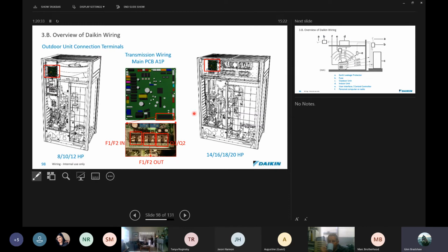Communication wiring in the outdoor unit. These are found on the control PC board, the A1P PC board. You'll find that on the 8, 10, and 12 in this vicinity of the wiring box, and on the 14, 16, 18, and 20, you'll find it over here, the terminal strip in the bottom right corner. They're designated F1, F2 in, remember, going to the indoor units, F1, F2 out, going to a centralized controller or my laptop, or the Q1, Q2, which would connect to other condensers in the combination.